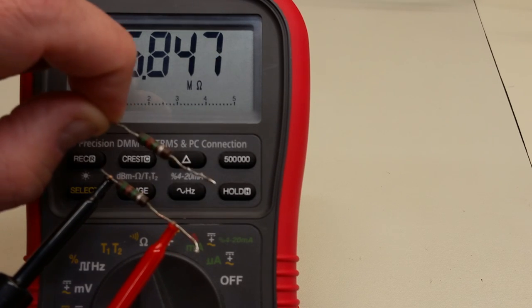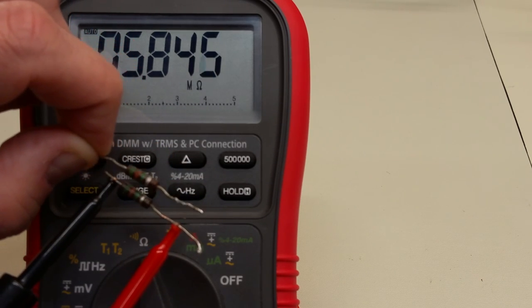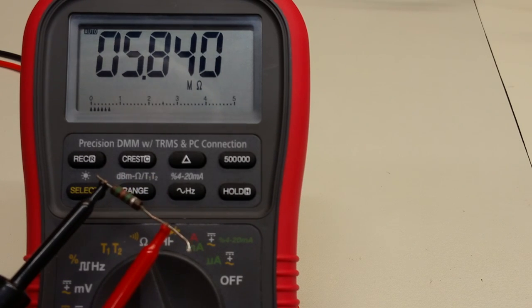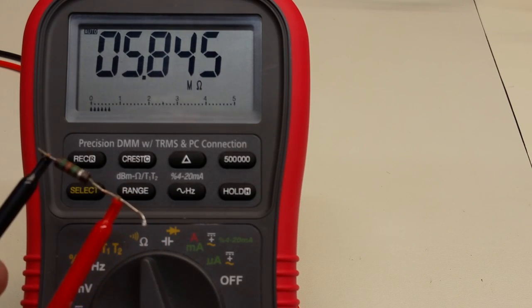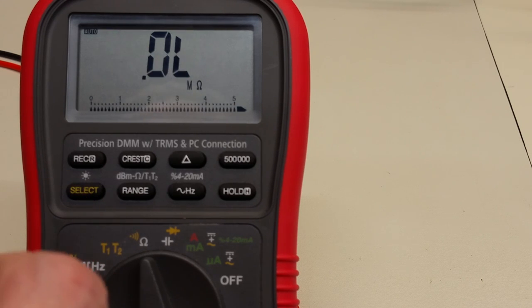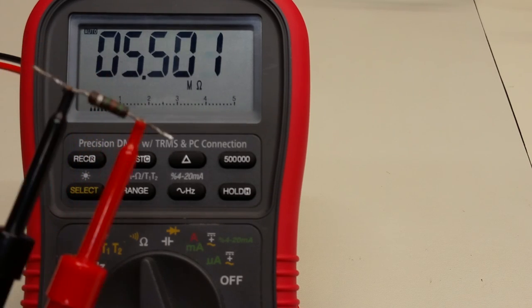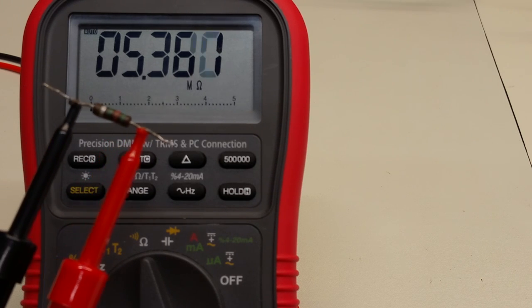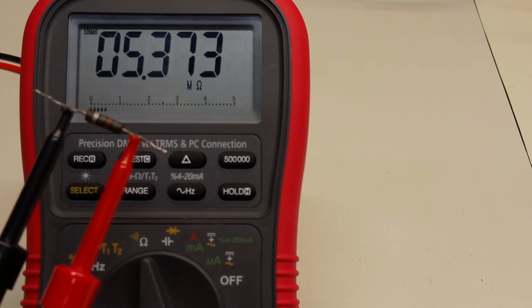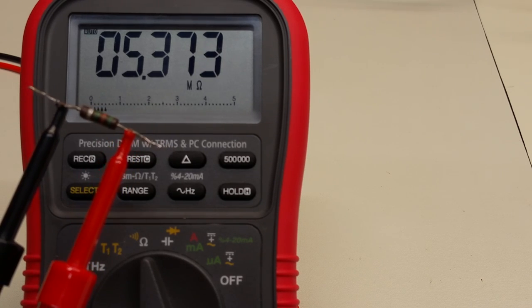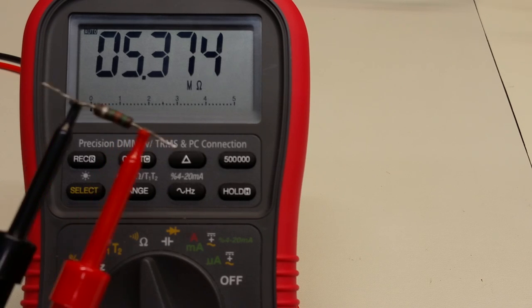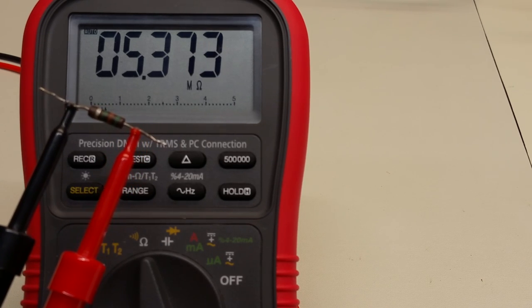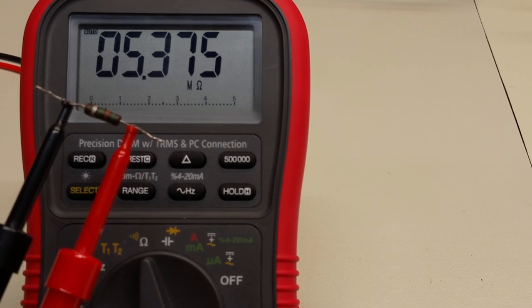Here is a resistor that I clipped out of the same instrument, and it was actually on just an opposite leg of the same circuit in this instrument. And we'll see if this also reads 5.8 megaohms. So I'm going to clip this in here and read it. And you see that this resistor actually is in tolerance. This is 5.3, 5.4 megaohms, which is lower than the 5.61 megaohm upper band. So it would have been fine to have left this resistor in the circuit. This hasn't drifted out of tolerance.